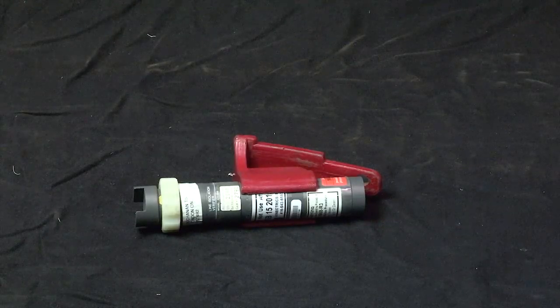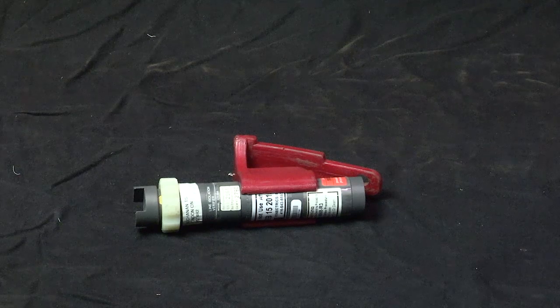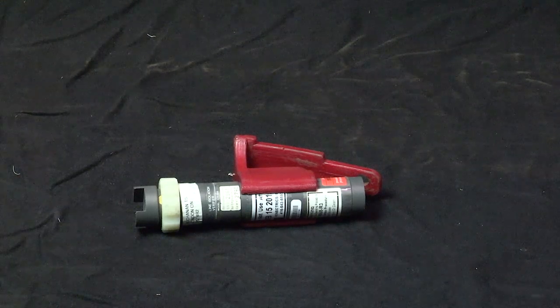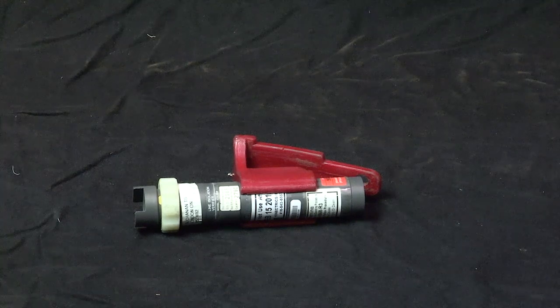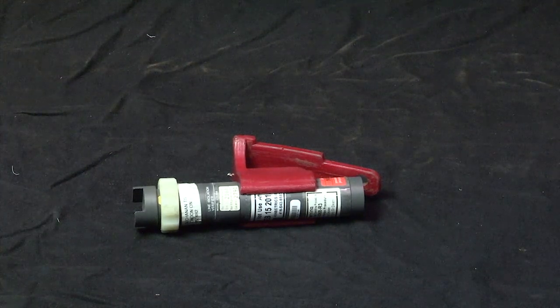An LIV is a line isolation verification device. It is a portable, small, lightweight instrument that detects the electric field on overhead or underground distribution and transmission lines in the range of 200 volts to 550 kilovolts. The function of this device is to verify if a line is isolated and safe to ground.